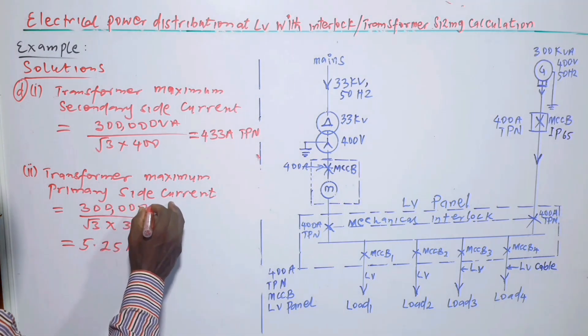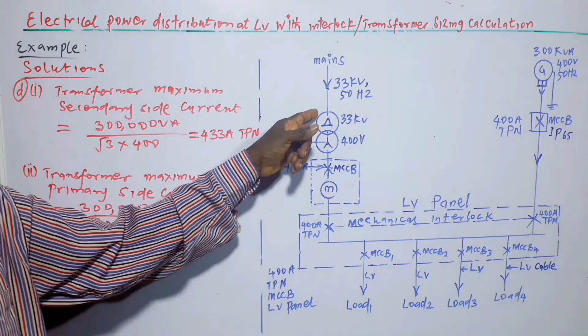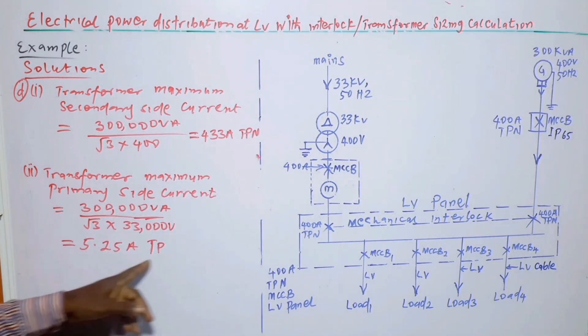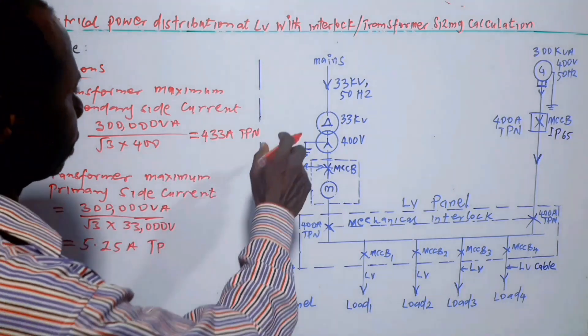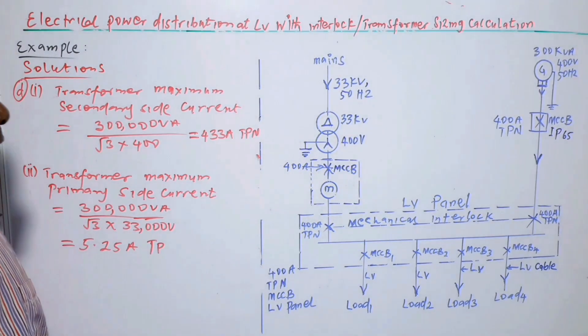So with that in mind, transformer maximum primary side current is equal to 300,000 VA divided by root 3 times 33,000 volts. Since the primary line voltage is 33 kV, the answer is 5.25 A triple phase. Triple phase in the sense that there is no neutral on the primary side because that is the delta side. And that is the end of the last part of the question.